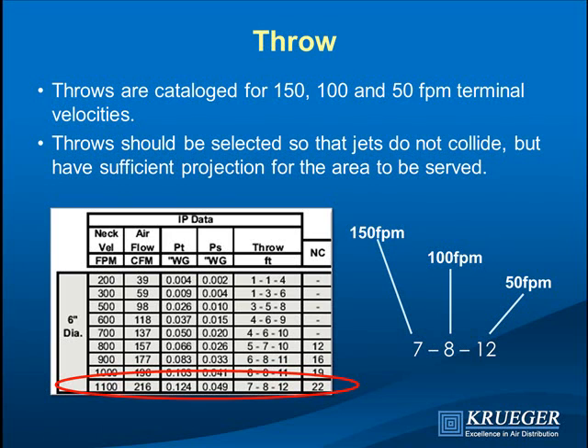Our goal is to select diffuser spacing so that at full airflow, the collision of the two jets from opposing diffusers does not come down far enough to enter the occupied zone. Typically, the 50-feet-per-minute throw plus about three feet, with a nine-foot ceiling, is what you want at the midpoint between diffusers at full flow. At turndown, you want enough throw that air will still serve people at the midpoint between diffusers.